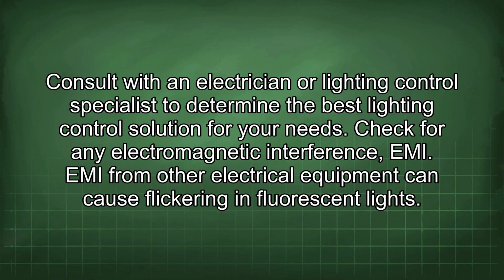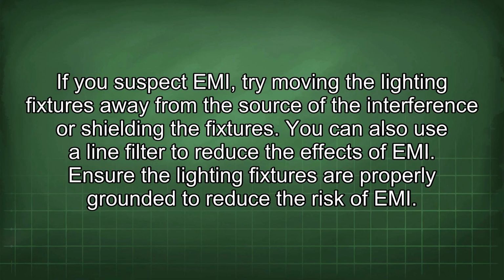Check for any electromagnetic interference (EMI). EMI from other electrical equipment can cause flickering in fluorescent lights. If you suspect EMI, try moving the lighting fixtures away from the source of the interference or shielding the fixtures. You can also use a line filter to reduce the effects of EMI. Ensure the lighting fixtures are properly grounded to reduce the risk of EMI.